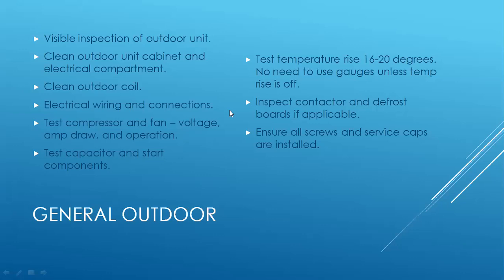And then once you're kind of done with your cleanings, at that point you can fire everything back up, do a temperature rise. You're looking for something 16 to 20. 16 is probably the lowest you want to see, and 20 to 22 is what you want to see. Difference between the supply and the return. If you've got a 21 degree temp split, I wouldn't necessarily put gauges on because you probably don't need it because it's looking good as it is. But if you're at like a 14, you might want to put the gauges on there and see what's off with it.